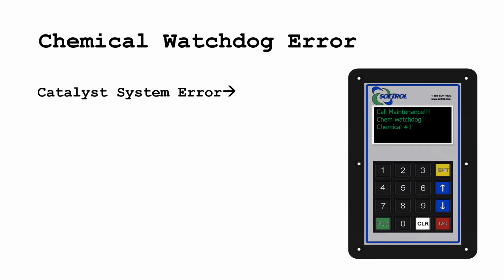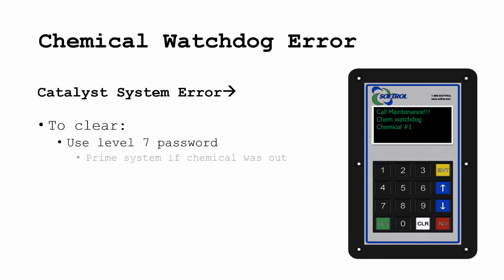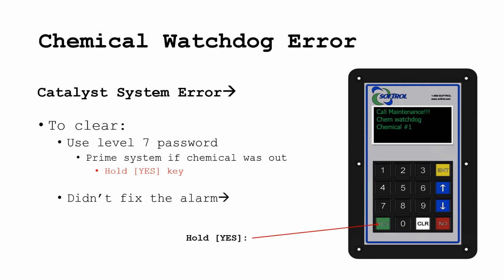If it is a catalyst system error, clear it by entering the level 7 password to reset the system. If the system was out of chemical, change the drum and prime it before beginning normal operations by holding down the yes key. If the system was not out of chemical and the alarm is triggered again, it is most likely a hardware error, which is addressed next in the video.